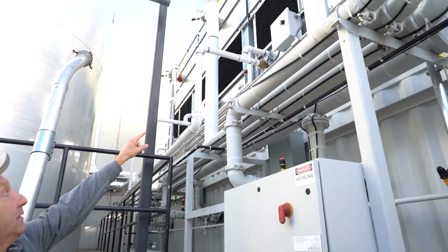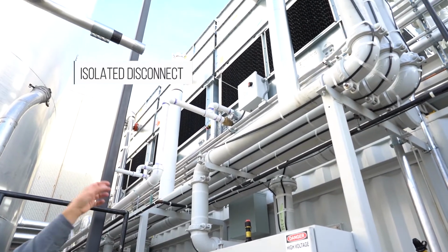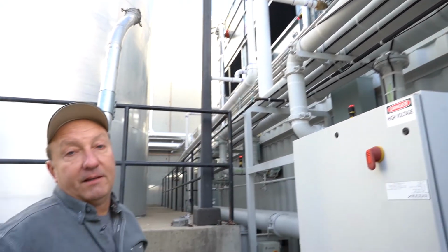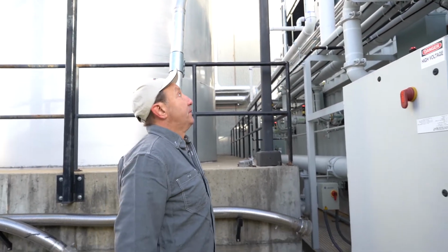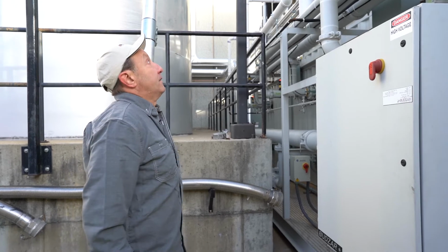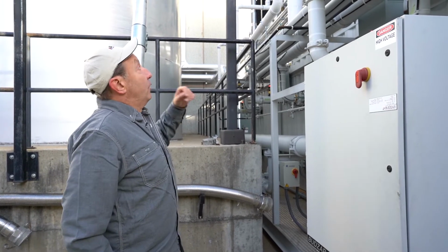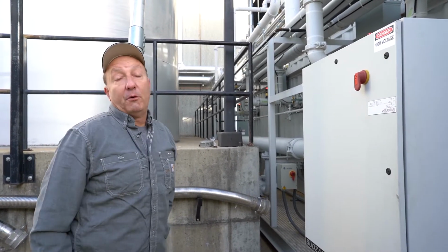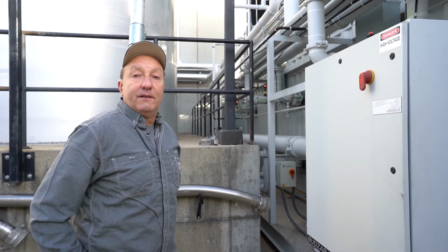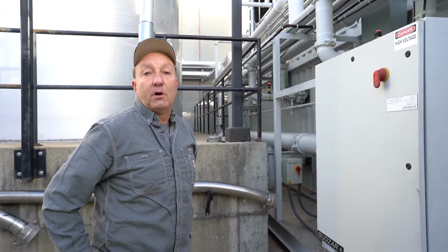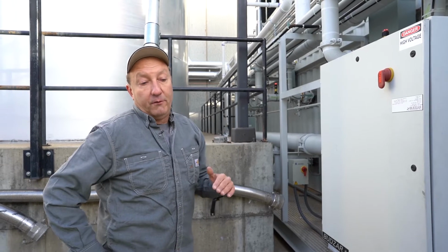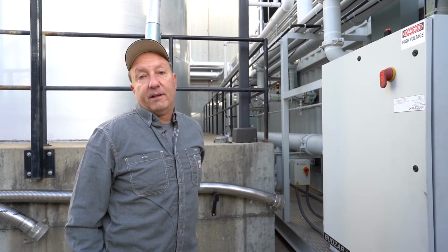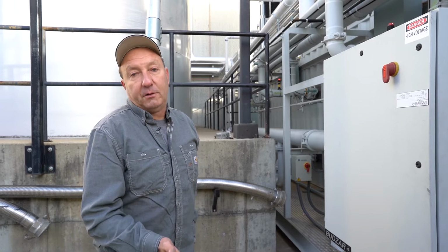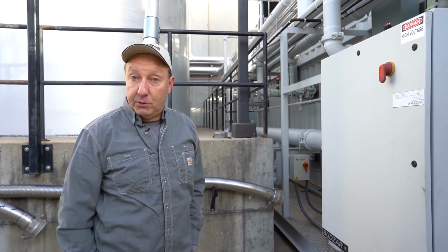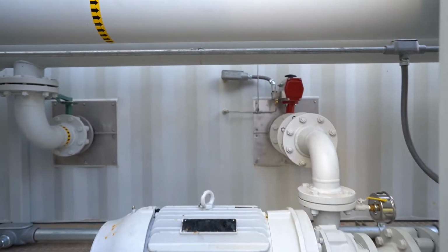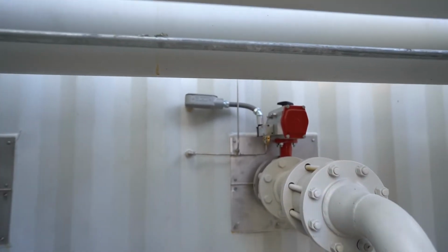Each one has an isolated disconnect, so you could turn off the power and maintain or work on the system for troubleshooting purposes or for routine maintenance. They are controlled by a temperature element that is set for 45 degrees Fahrenheit. So in the event that the tower system is not in use or off, if the water gets below 45 degrees, the heater is enabled at that point and stays on until the temperature comes above 45 or is in use. Okay, each circuit, as I stated, each one is an independent chiller circuit.